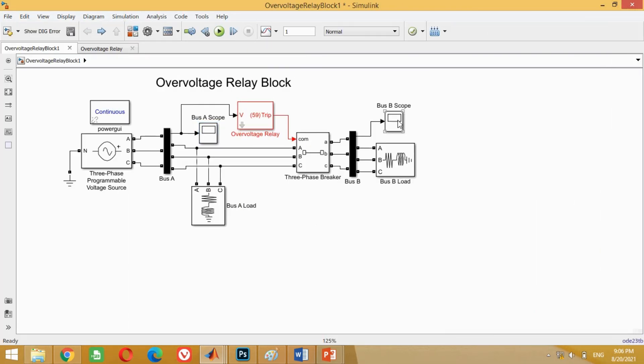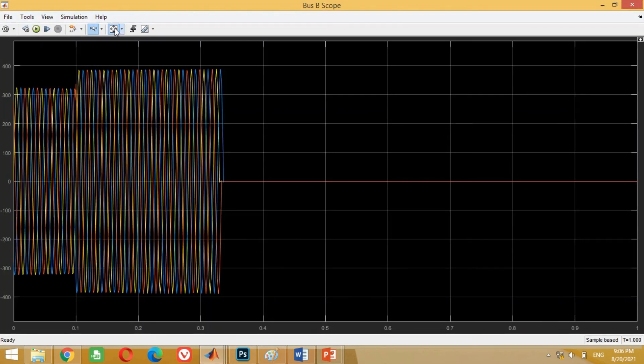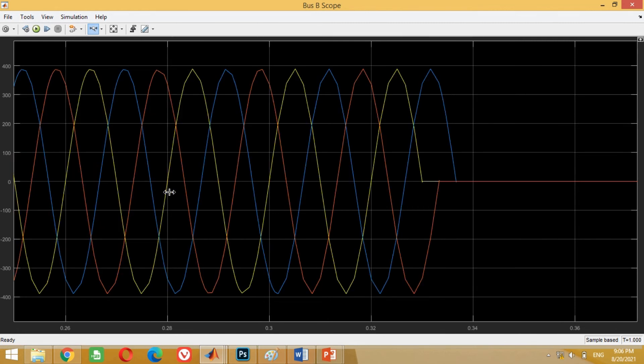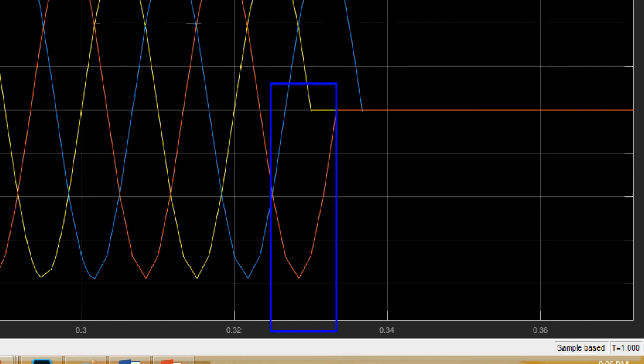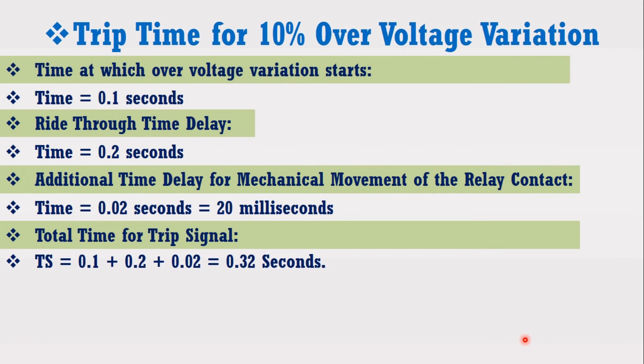Double click on Scope B at Bus B to check its voltage. You can see it shows that the overvoltage relay has successfully operated and disconnected the load. At 0.33 seconds, the overvoltage relay has disconnected the load. Comparing the trip signal time with the mathematically calculated time, both times are almost accurate. This means that when the system voltage rises to 10% of the original voltage, the overvoltage relay successfully detected this voltage rise and disconnected the load at 0.33 seconds by sending the trip signal to the circuit breaker.